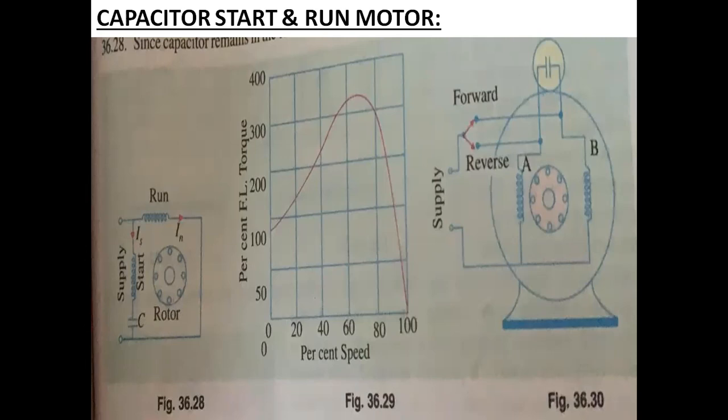There are two types: we can use one capacitor for both running and starting purposes, or we can use two capacitors — the first capacitor for starting and the second for running. If we start with two capacitors, we start with a high value of capacitance and switch to a low value for running. This is called a two value capacitor run motor. If using a single capacitor, it is a single value capacitor run motor.